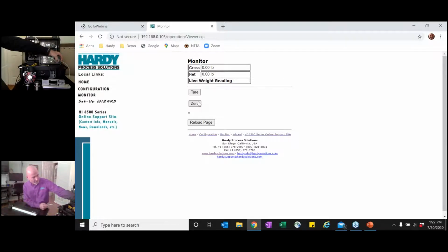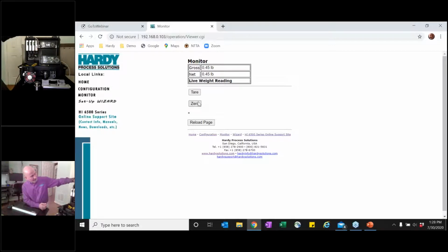Now we'll go in and say we want to do a low calibration. It says that right now there's 0 pounds on the scale, but it says my low calibration weight is at 1.7 pounds. Now I can go in and change that, but I'm going to leave it. What I'm going to actually do is put 0.45 on the scale. So we've got it here, we've got it here, we've got that on the monitor. So let's go in now and say do the low cal.